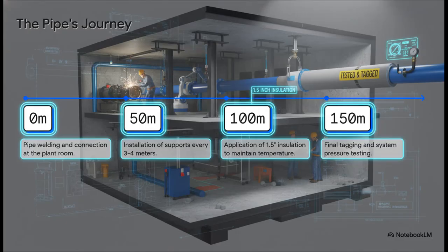You can really think about the piping installation as a journey in itself. It starts with incredibly precise welding down in the plant room. Then, as the pipes snake their way up through the building, you've got these heavy-duty supports going in every 3 to 4 meters to handle the immense weight. After that comes the really critical 1.5-inch insulation wrap, which keeps the water ice cold on its trip. And finally, everything gets tagged and tested. Every single step has to follow strict industry standards, like the ones from SMACNA.